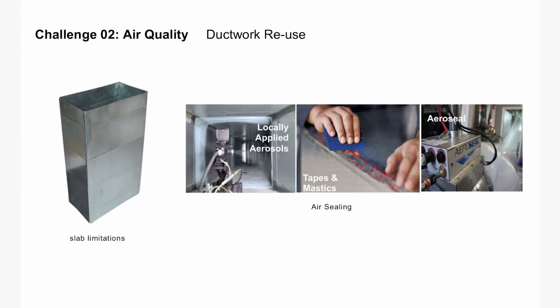The last one is a technology called AeroSeal, developed by research facilities in the States. It's a polyvinyl chloride substance that only adheres to leaks in the ducts, so it doesn't coat the duct and it doesn't remain in the system, but it can eventually accumulate in a leak and block something up to 3/8 of an inch.